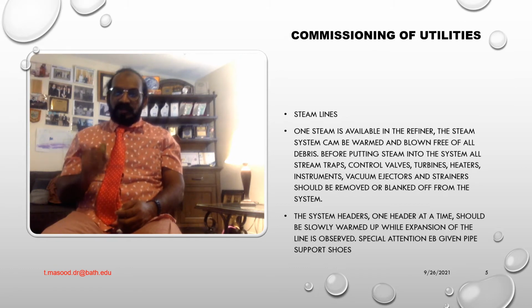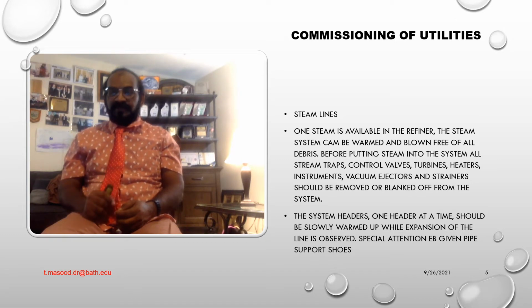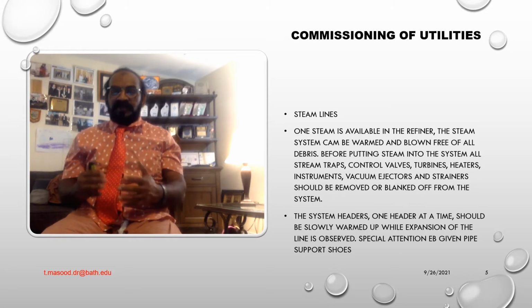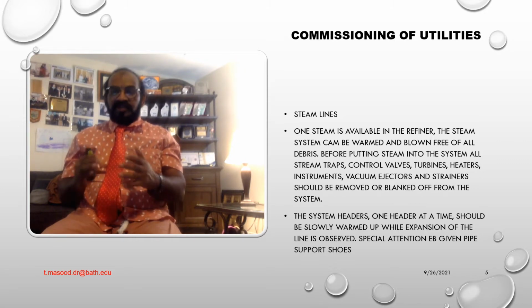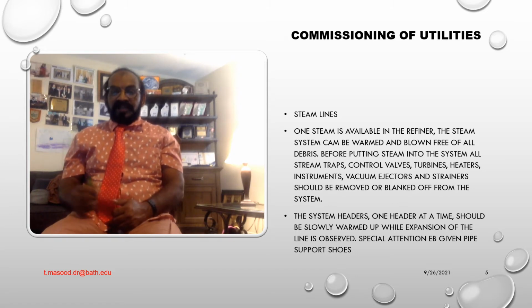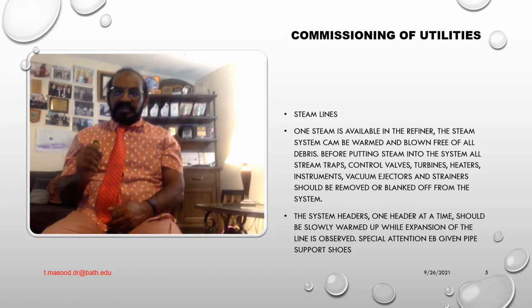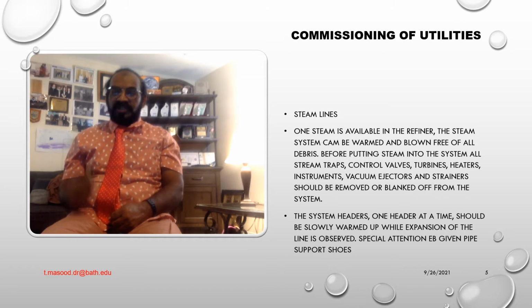When the headers are warm, the drain and vent valves should be opened and the lines blown vigorously for a few moments before reclosing the valves. This procedure should be repeated 5 to 10 times to move materials along the headers to the drains. On the turbine lines and headers, special attention to detail is critical. All debris, including scale, must be removed from those lines, otherwise there will be damage to the turbine blades. Blow these lines clean using high velocity steam and alternate the temperature of the line so the scale on the pipe wall is removed.